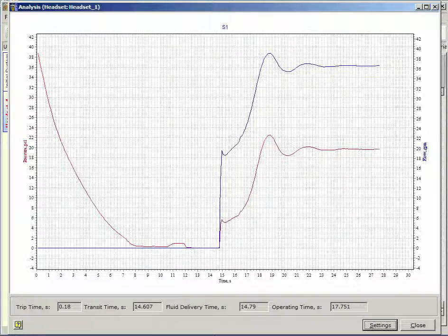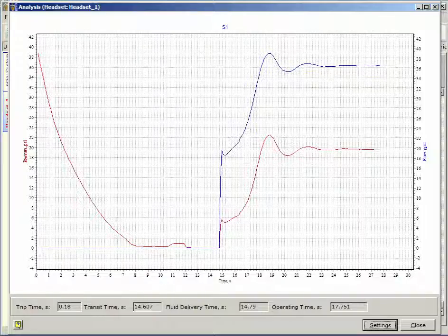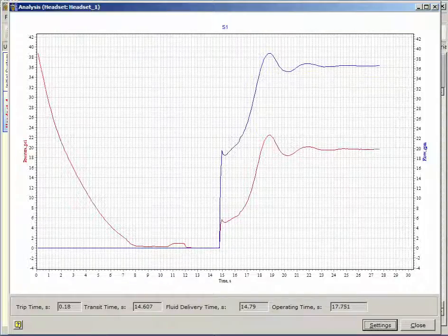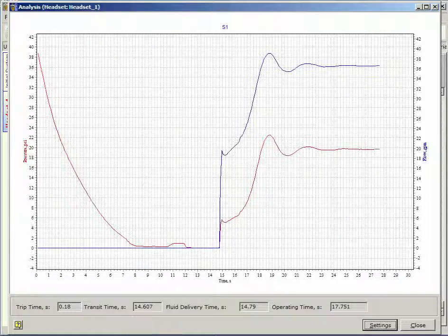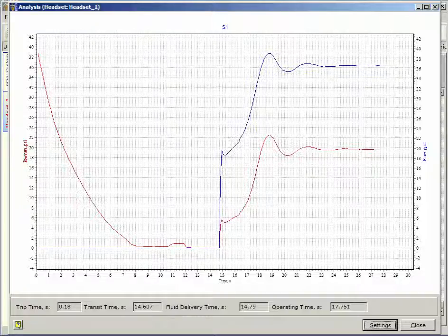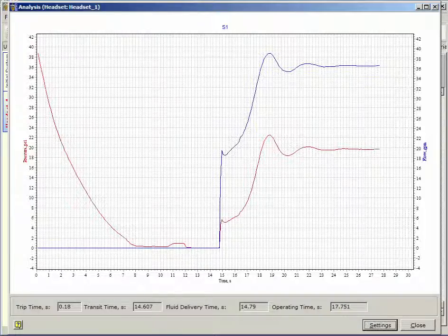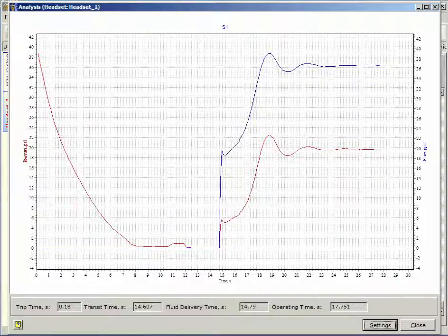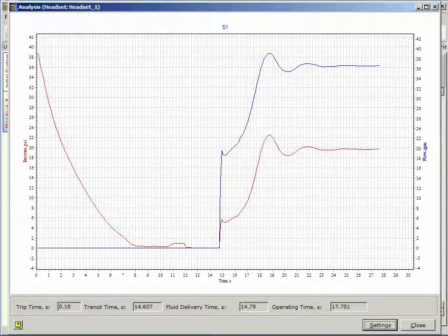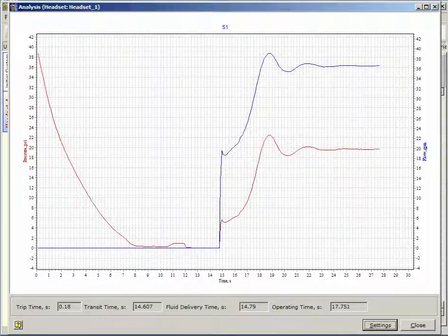The example here shows a head. At zero time, the gas pressure is at 40 psi as set in the calculation dialog box. The open sprinklers begin to vent gas and the pressure goes down. The dry pipe valve opens almost immediately and the pump switch starts the 10 second countdown. The gas pressure continues to decrease. The water has entered the system and is rushing toward the open sprinklers. A pressure spike occurs when the fluid reaches the sprinkler due to the water hammer. The pressure spikes again because the pump has started.